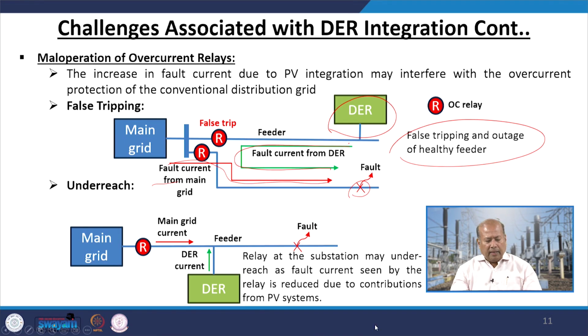Now, in case of underreach, the relay at the substation may underreach as the fault current seen by the relay is reduced due to contribution from the PV system. Whatever the main grid current you see, now you also get some DER input here. So the fault current seen by the relay is reduced due to contribution from the PV system.